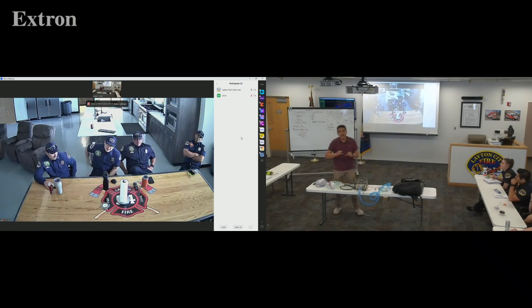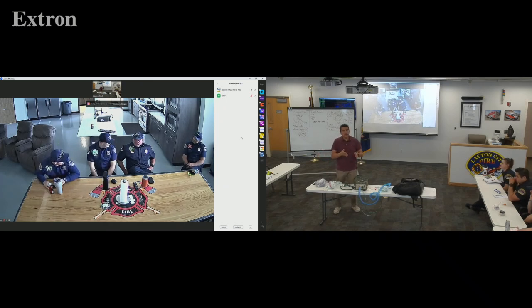Historically, ventilators have a time of 1 to 2 minutes to figure out the changes that you're making and give you a good responsive result within that time. So if you make a change on a ventilator and you change it every 2 minutes, are you giving it the time to give you a positive response? No. So please slap your paramedic partner's hand if they're like 25, oh it's not working, 30, it's not working, 35, it's not working, within that 2 minutes say, quit it. 25, leave it alone, give it 5 minutes, if it's not working, then do something different, right?